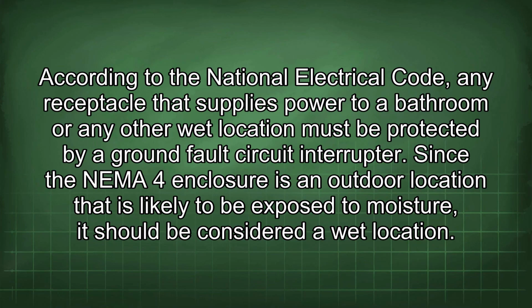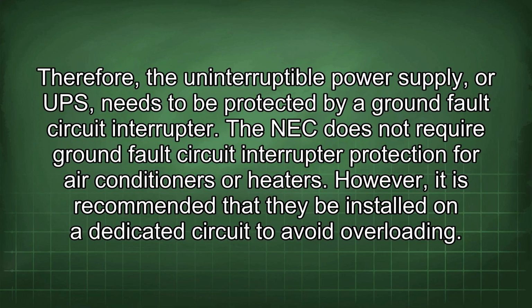According to the National Electrical Code, any receptacle that supplies power to a bathroom or any other wet location must be protected by a ground fault circuit interrupter. Since the NEMA 4 enclosure is an outdoor location that is likely to be exposed to moisture, it should be considered a wet location.